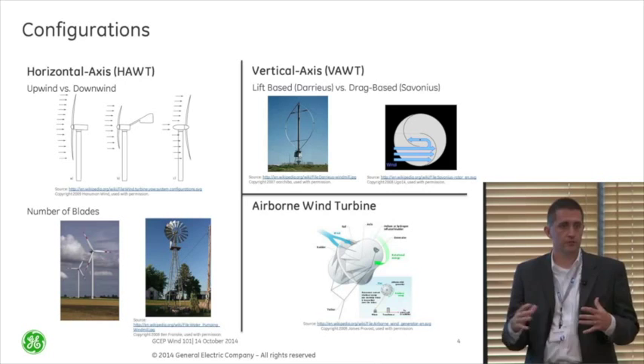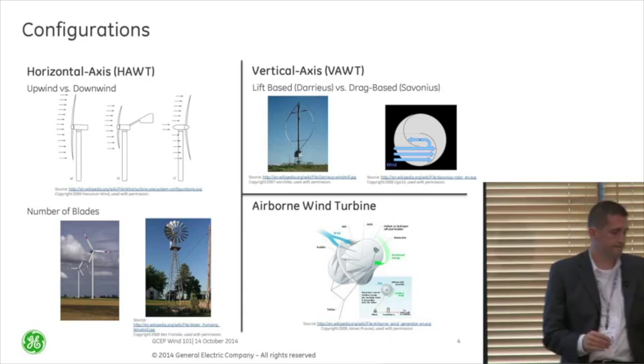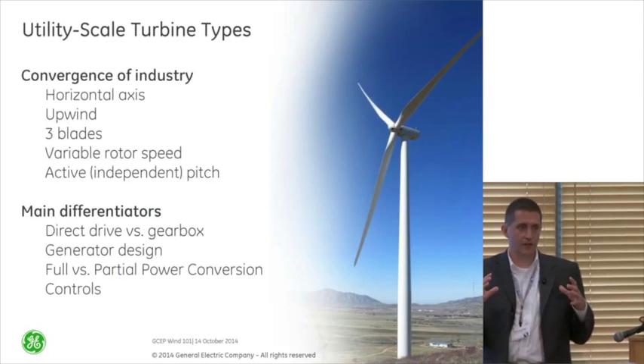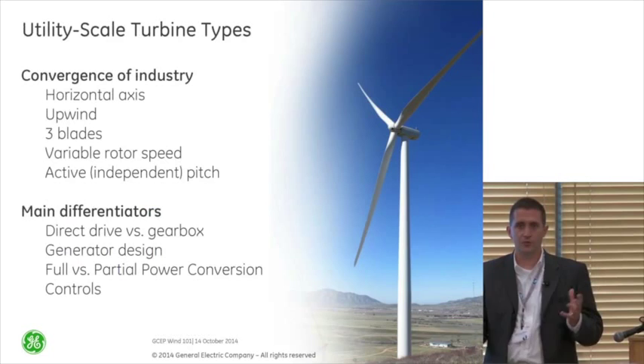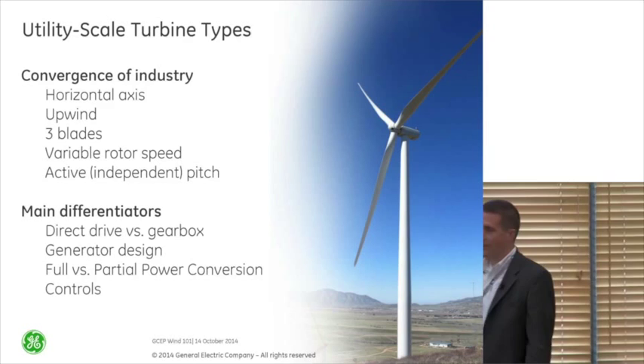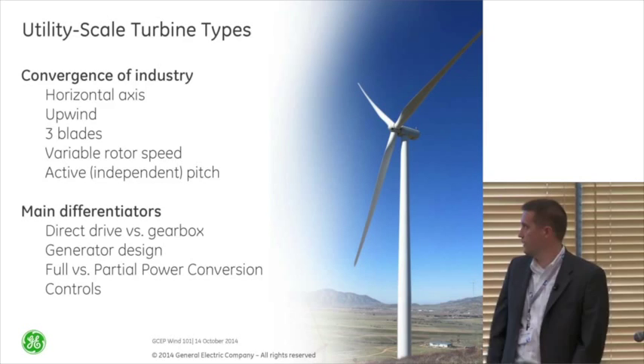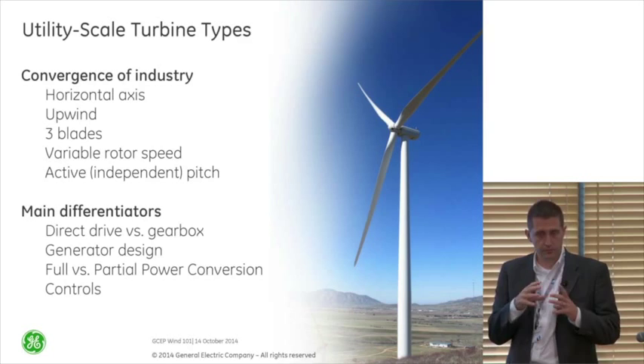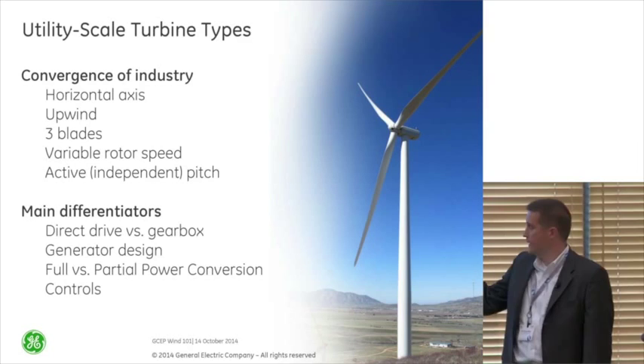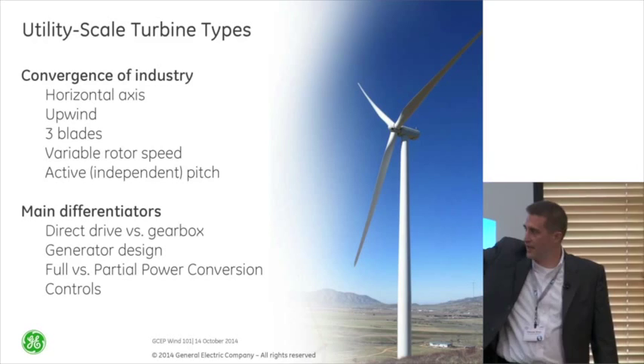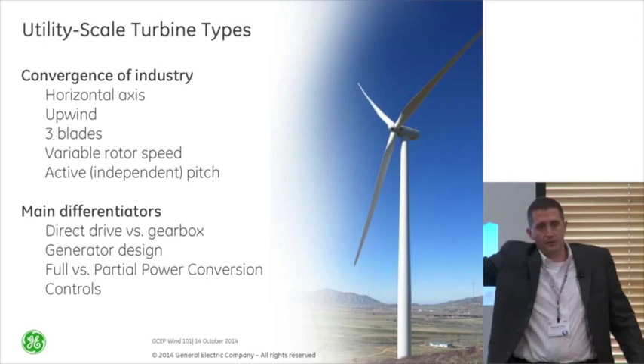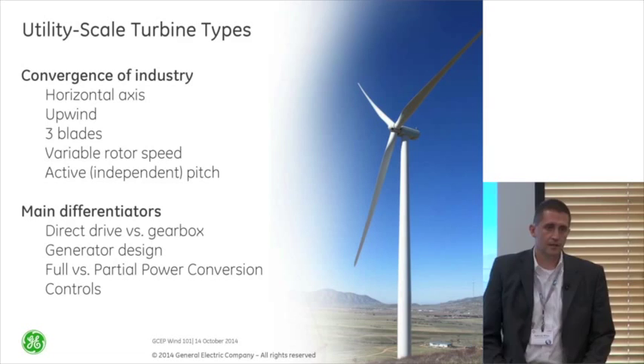I want to quickly ground you on where the industry has converged to. You've probably driven by and seen wind turbines — they're horizontal axis, upwind, three blades almost all the time. The rotor speed is variable. They have what we call active pitch — the blades have an aerodynamic shape, and we're able to turn them with a pitch mechanism to control rotor speed and feather them out of the wind when we get high wind speeds, making sure we don't create too many loads on the turbine.